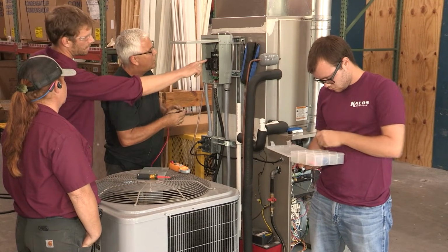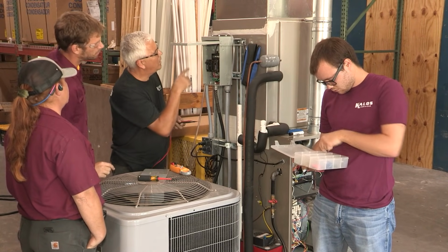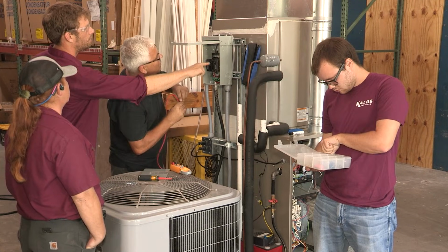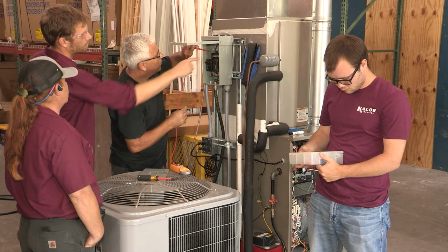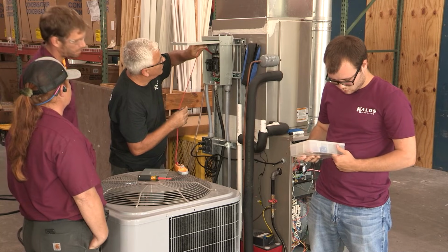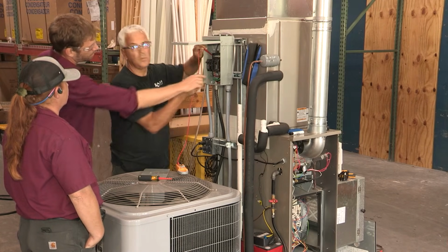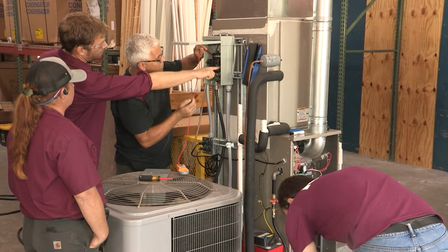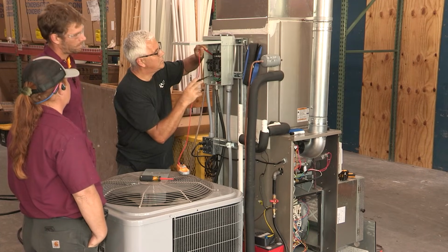Between hot and neutral. We have incoming power first, right? Yep, go ahead and check the incoming power first. That's not actually our incoming, that's our condenser. Your incoming is going to come into the top of the bus bar, and you have 240 and then neutral. So let's check our 240 first.